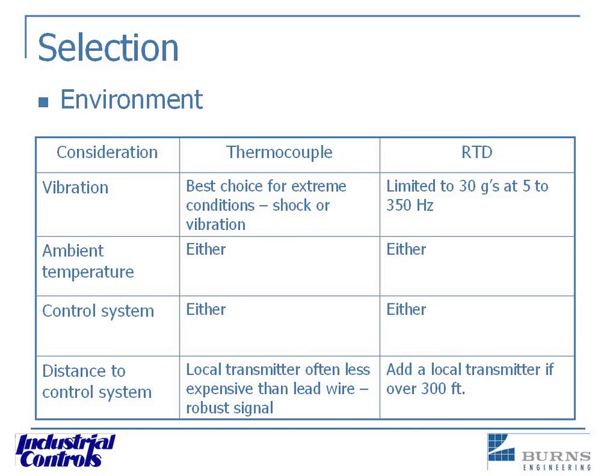And the thin films are going to be more resistant to vibration just because of the way they're constructed. That thin layer of platinum that's on that ceramic substrate is bonded to it fairly well, and it can't really move around very much. And the key with getting a very vibration-resistant sensor package with a thin film has to do with how the thin film is supported inside the temperature probe. There are several different potting techniques and supporting techniques to do that. And when it's done correctly, they can be extremely durable.